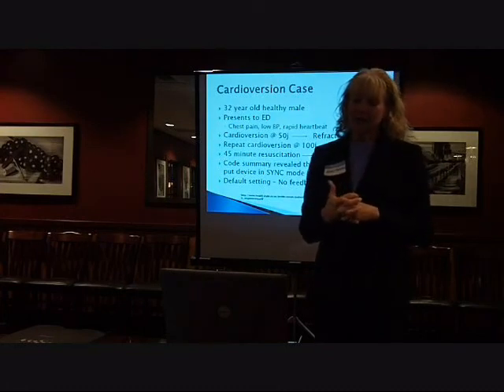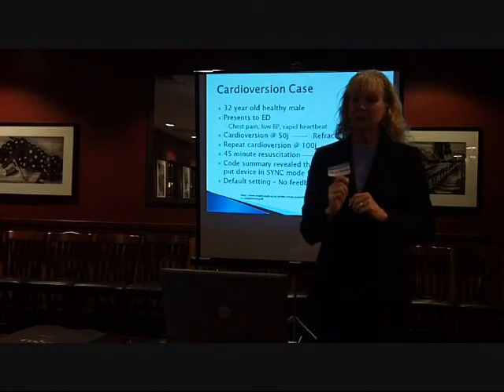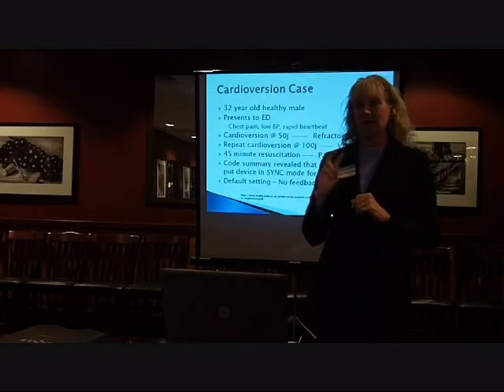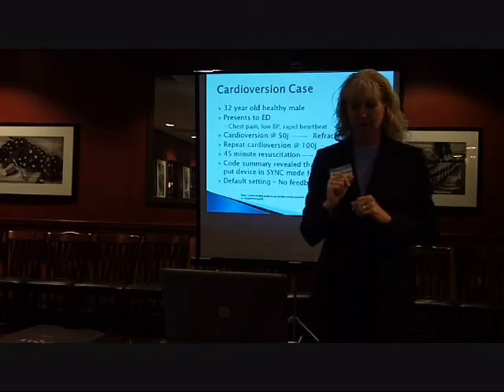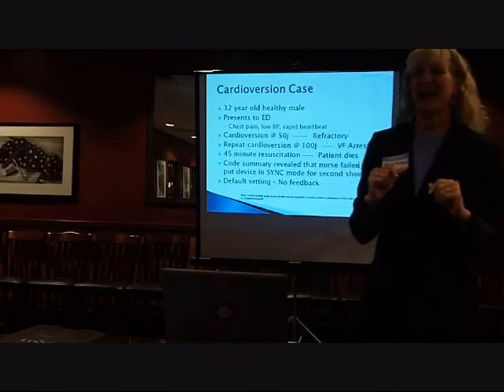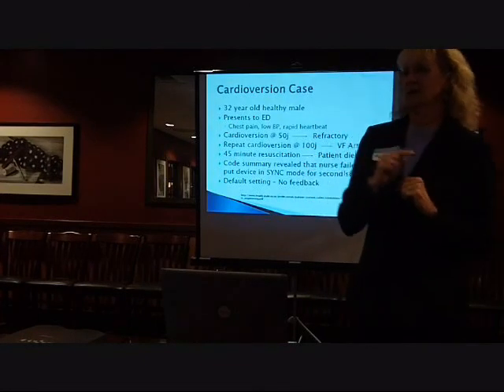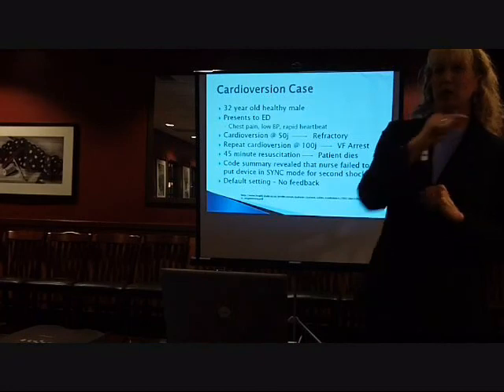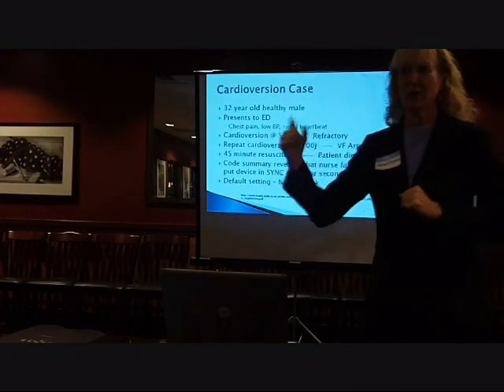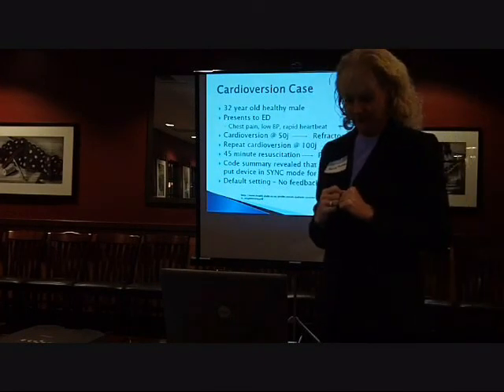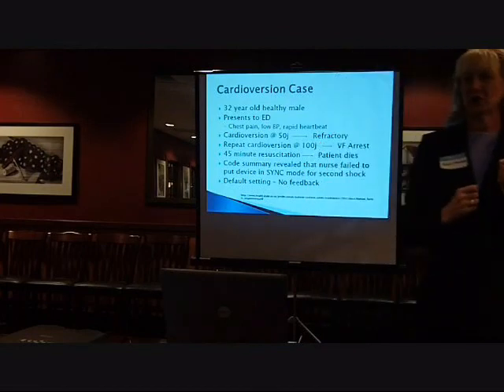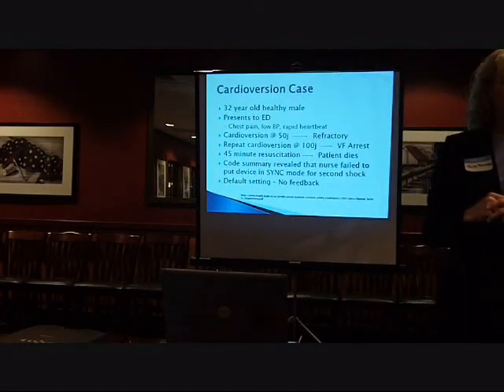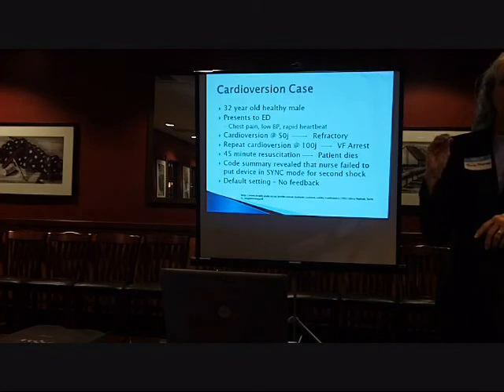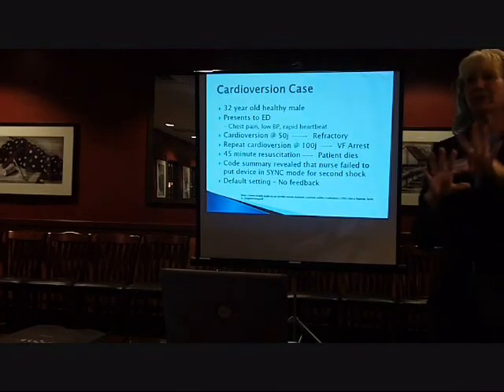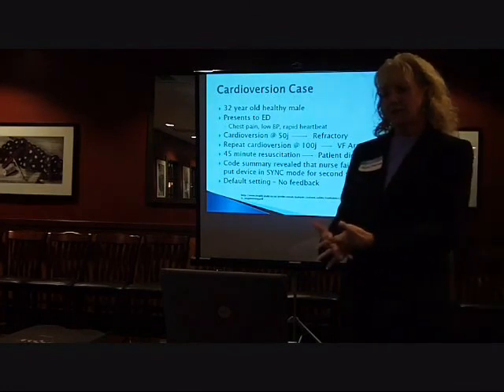So they go back and look at the summary, and they reveal that the nurse failed to put the device in the sync mode for the second shock. So there's a default setting. After you shock, it doesn't go to the sync mode. You've got to put it in sync mode in order to do your second shock. There's no feedback that tells you this. There's no warning, there's no alarm, there's no "Hey, do you know you're not in sync?" No voice, nothing.